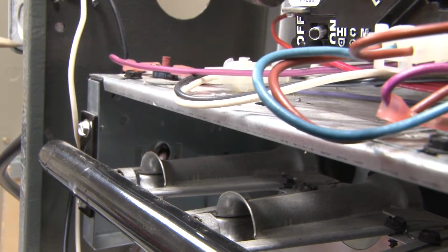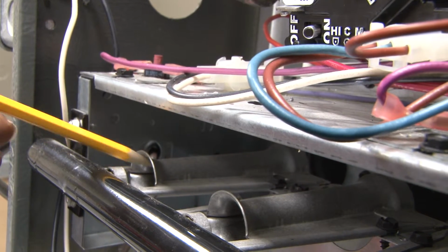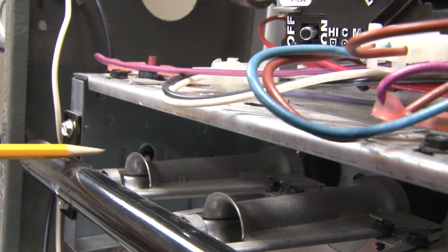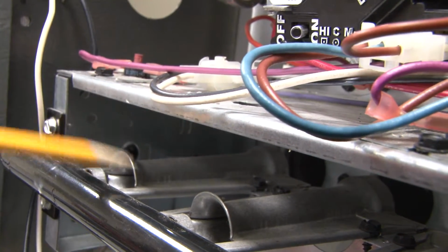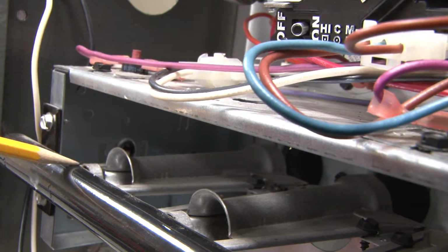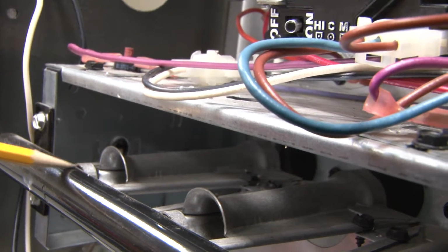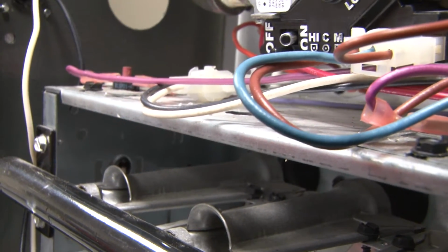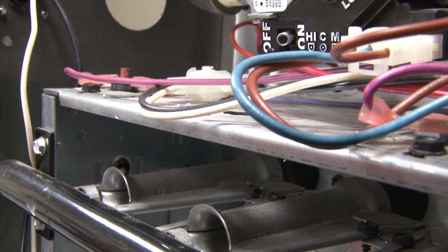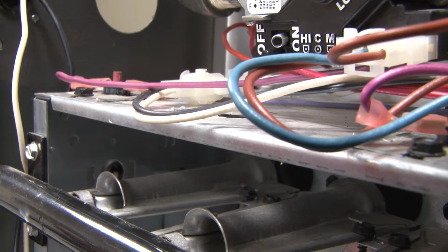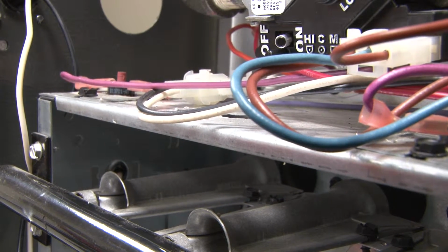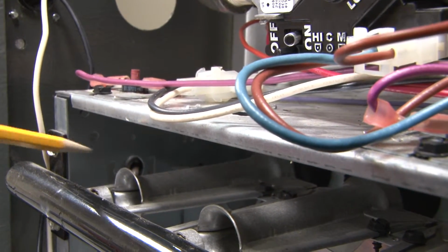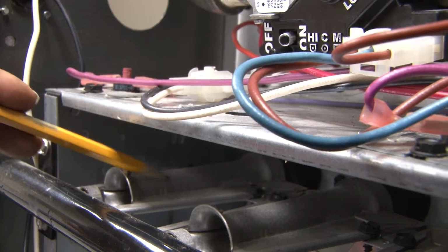So as the pressure increases, the speed of the air will increase and cause it to drag air to mix with the fuel. So this, at the nozzle, is a small opening in the orifice that under pressure will shoot a stream in, and it will help drag the air around it, which is stagnant, to move along with it and cause it to mix with the fuel at the right proper velocity and combination of air and fuel.